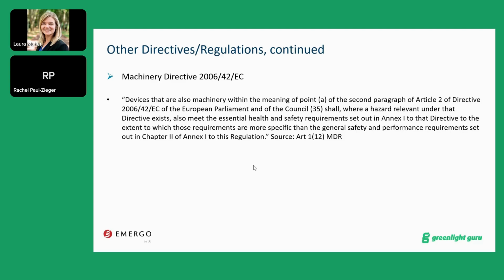But the fact is that it is recognized to be the best way to show compliance by drafting a tabular format, a table with each of the requirements. So by practice, this is now an expectation that manufacturers establish a GSPR checklist. This is something notified bodies and competent authorities are waiting for, and that they will ask for.